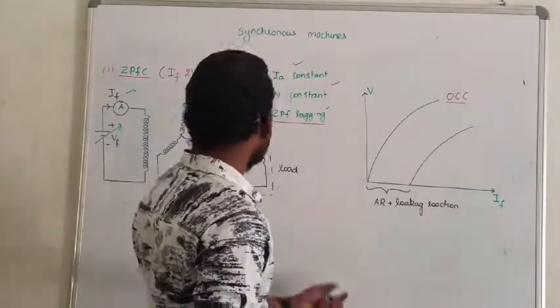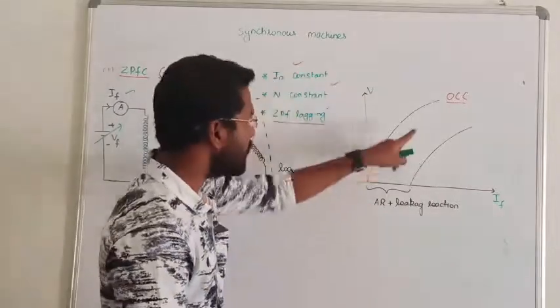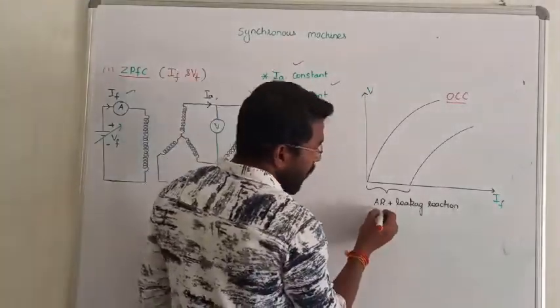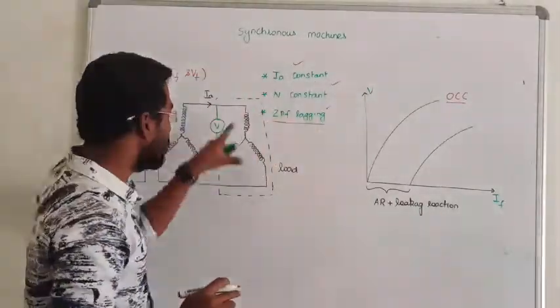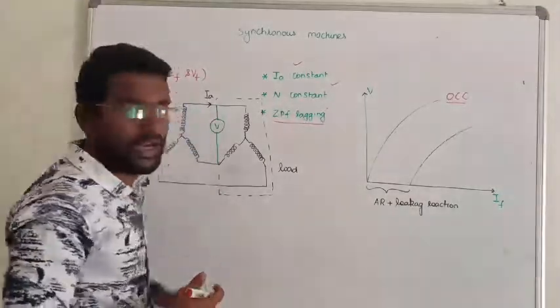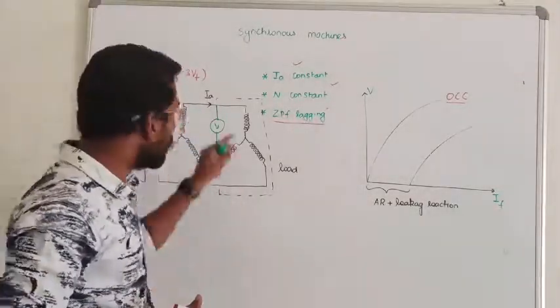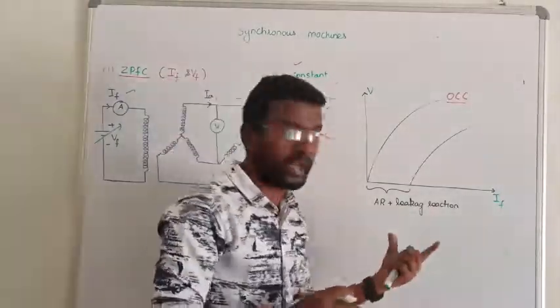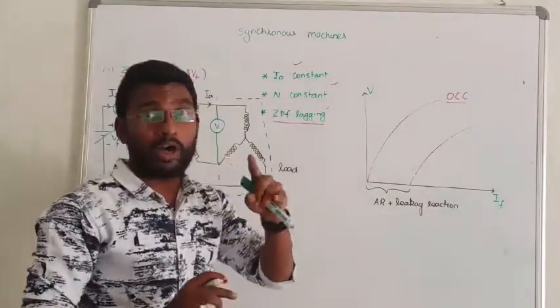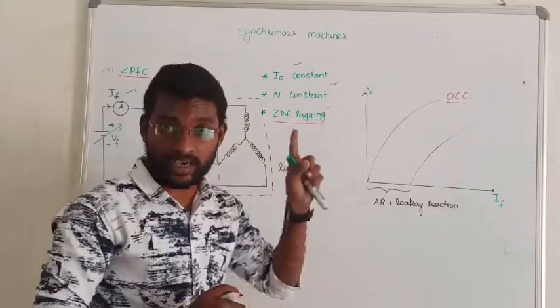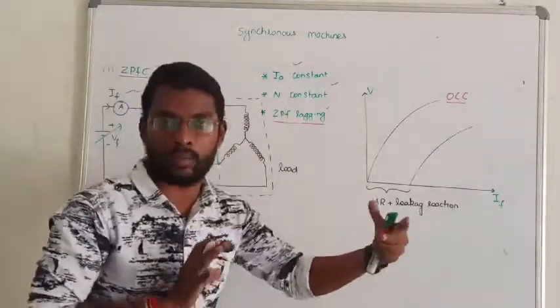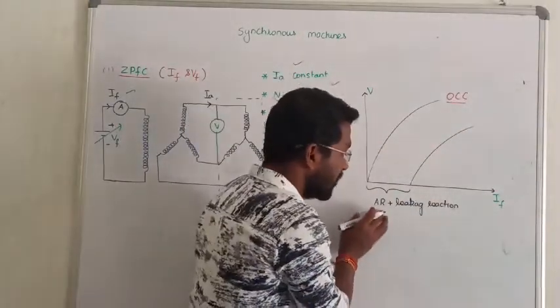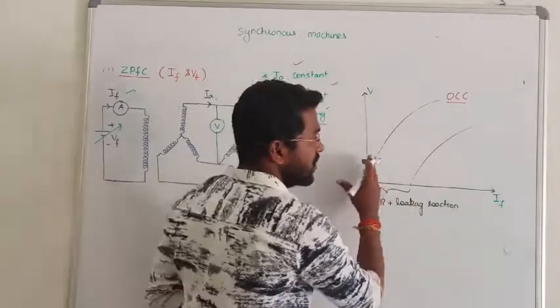If we consider zero power factor lagging, it is almost the same as open circuit characteristics. But what is the difference? In case of zero power factor lagging, armature reactions and leakage reactance are present when you have a load, and the armature current is constant. We are maintaining this armature current as constant. Due to the presence of load, this armature current is present — there is no armature current at no load. Armature current causes armature reaction; armature current and field current together produce armature reaction. This curve is the open circuit characteristics, but due to armature reaction and leakage reactance, this curve is shifted to some extent.